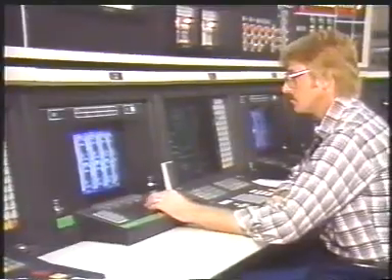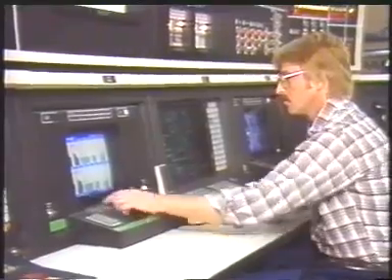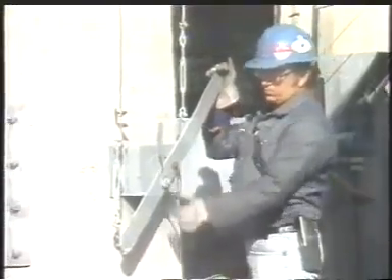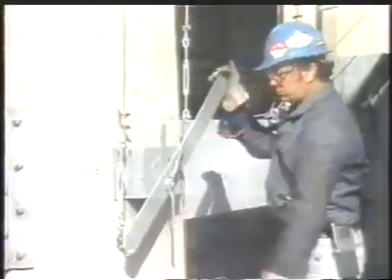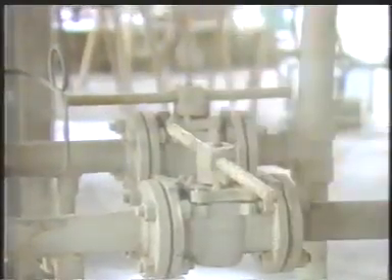During normal shutdown operations, the process flow rate and firing rate are gradually reduced together. When minimum firing has been reached, you shut off fires and open the PEEP doors. Process circulation is continued to cool down the tube slowly. Next, you open the stack damper and air registers to purge the furnace. Then block the fuel systems, including the burner and regulator valves.